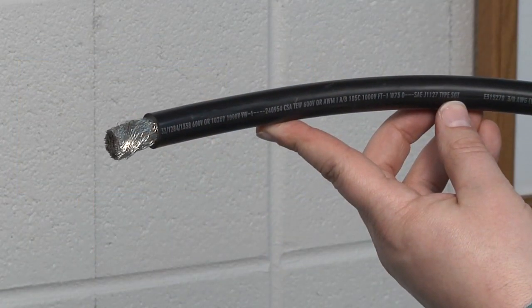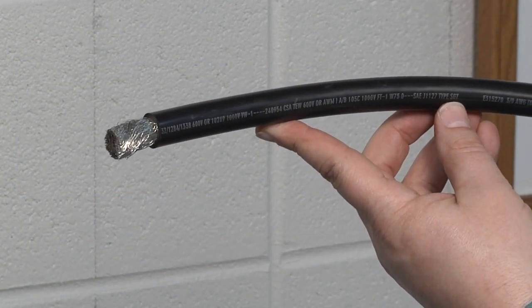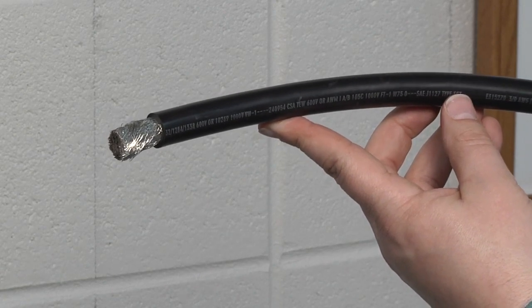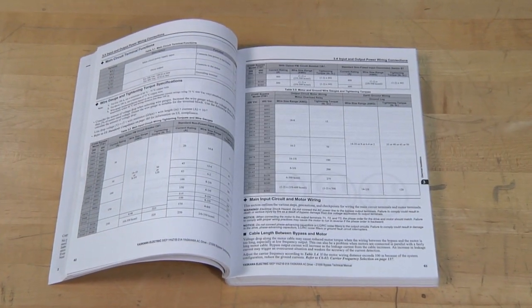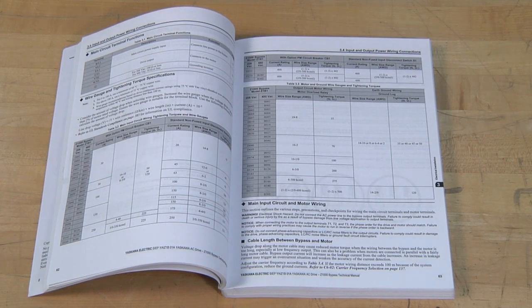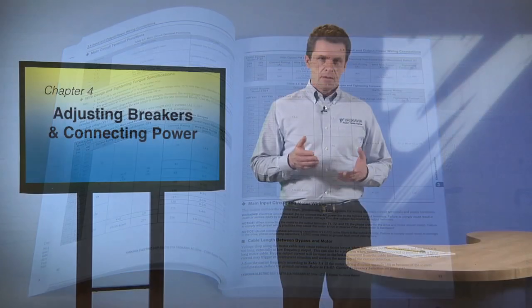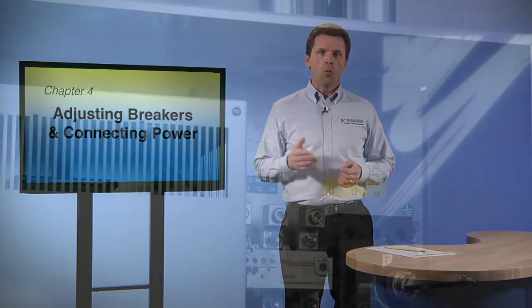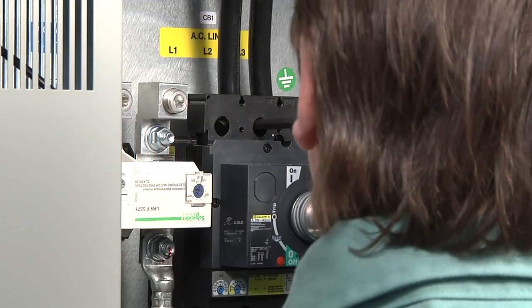Start this process by making sure you have the proper gauge of wire for the current your bypass is rated to handle. Consult the Z1000 Bypass manual for detailed information on the proper wire gauges. From your main disconnect, wire up the circuit breaker and the ground lug.